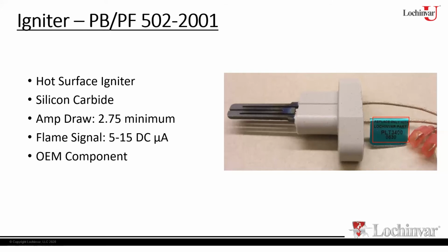Unfortunately, on this unit, you really can't check it. You're looking at the display. So the display is going to show you what that microamp signal is. Now, if you wanted to actually measure it, there is a way of doing it. I've never done it myself in the field, but it does involve using a shunt capacitor, a meter, and a couple other devices. I've got a wiring diagram around here somewhere for it, but there are actually no test ports on the board to measure it.